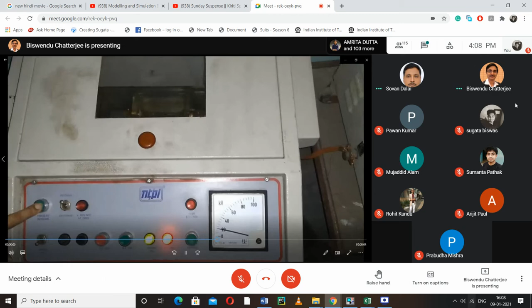And the basic logic behind that is that transient breakdown occurs because some impurities are attached to one of the electrodes and reduce the gap. But after the transient breakdown occurs, the chain formed with the electrode breaks and it regains its normal gap distance. So for that reason, after transient breakdown there is no trip in the circuit. Tripping is not there. From that also you can easily identify. Also, I think it is clear from the video.